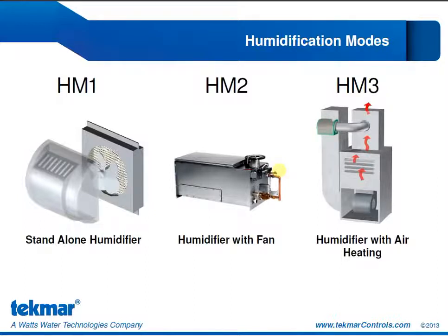There are 3 humidification modes in the 557. The first, mode 1, is for a standalone humidifier. An example would be a console unit that has its own fan to blow air through a wet medium and into the space. If a unit like this did not have its own humidistat, the 557 could enable it as we needed humidification.